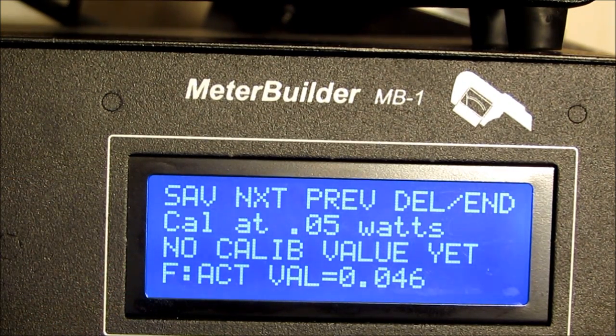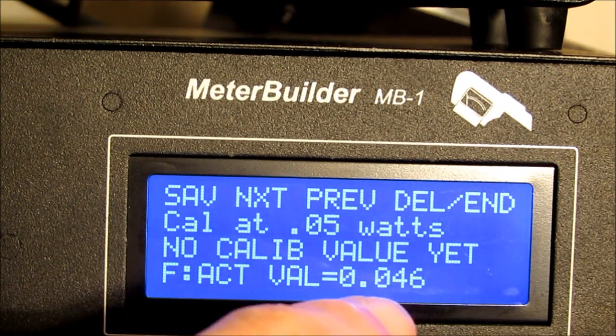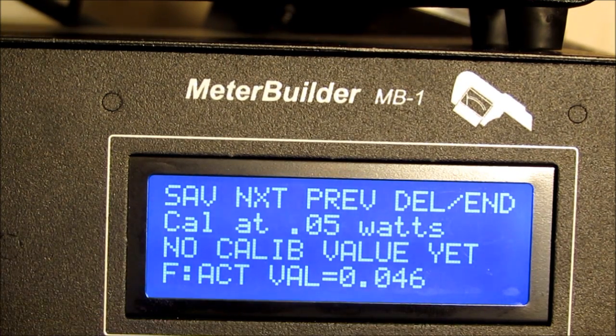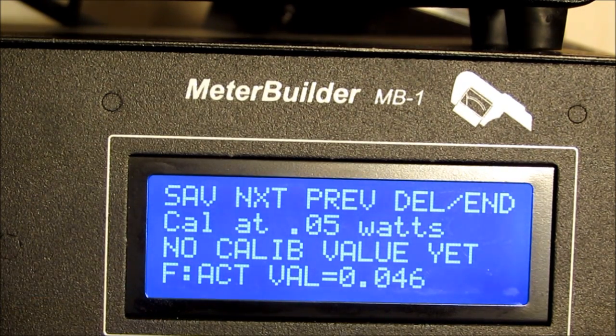What that's doing is performing a calculation by taking into account the actual power. It's assuming that I wanted to calibrate at 0.05. The actual power is 0.046 as an example in this case. And the calibration constant that it will pop into the 0.05 watt calibration slot will be more accurate than if we hadn't provided this capability of specifying the actual power. So let's go ahead and try to do a calibration at 0.05 using the reference meter as a guide.